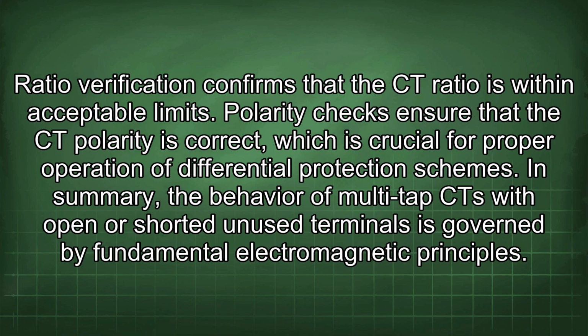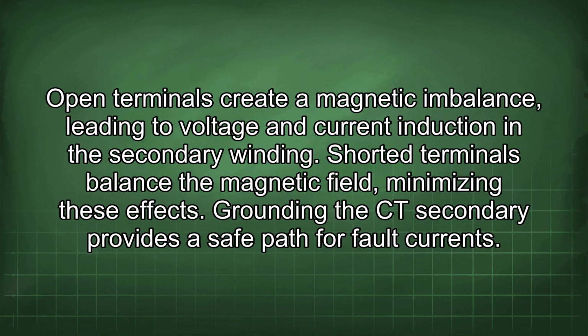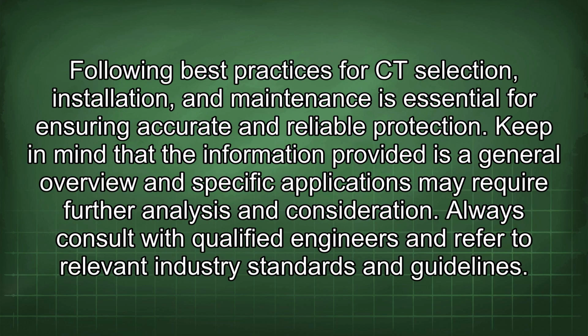In summary, the behavior of multi-tap CT with open or shorted unused terminals is governed by fundamental electromagnetic principles. Open terminals create a magnetic imbalance, leading to voltage and current induction in the secondary winding. Shorted terminals balance the magnetic fields, minimizing these effects. Grounding the CT secondary provides a safe path for fault currents. Following best practices for CT selection, installation, and maintenance is essential for ensuring accurate and reliable protection. Keep in mind that the information provided is a general overview and specific applications may require further analysis and consideration. Always consult with qualified engineers and refer to relevant industry standards and guidelines.